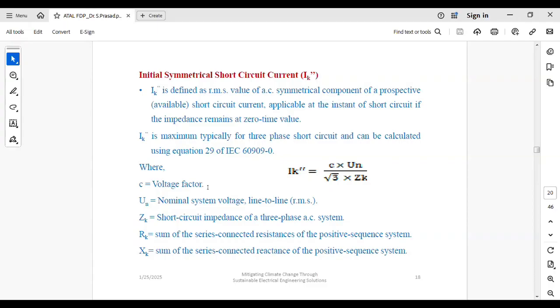Why is the minimum short circuit test also conducted? Because when you do relay coordination, the coordination of the protecting devices, we set the relay settings based upon the minimum short circuiting current, not the maximum value. For reliable operation, to make it more sensitive, we set it at the minimum level, not at the maximum short circuiting current level. So when conducting the short circuit analysis, you have to consider both the maximum and minimum short circuiting cases.